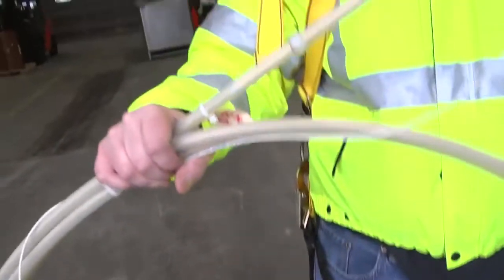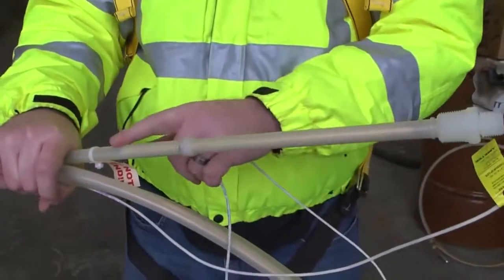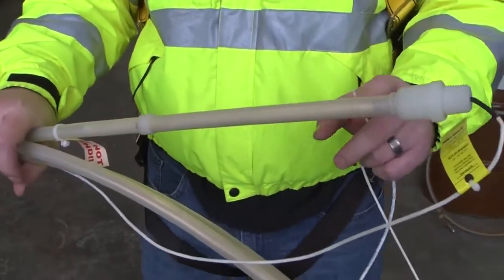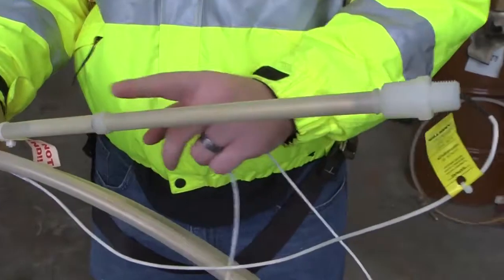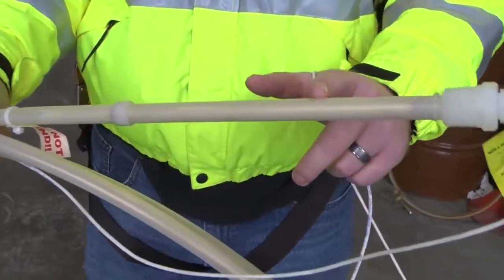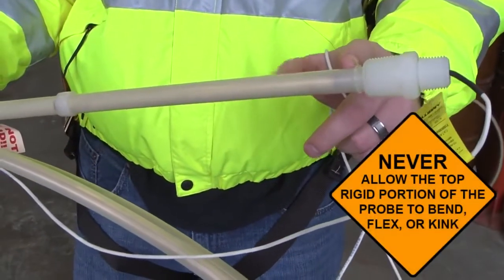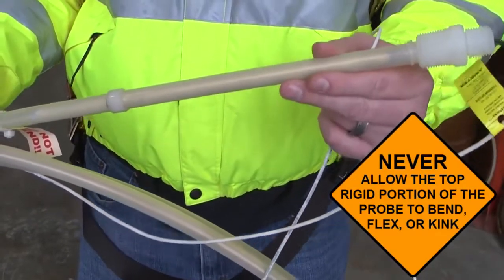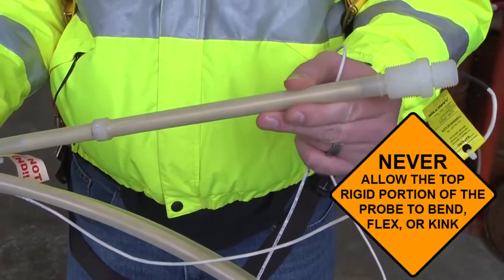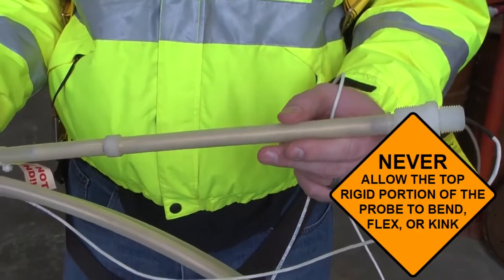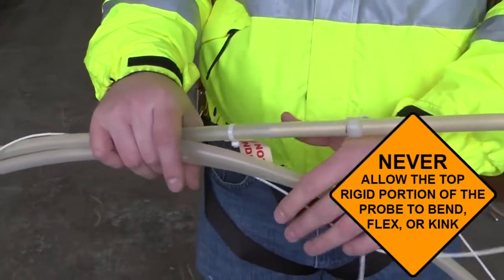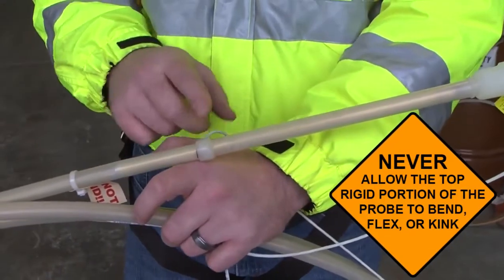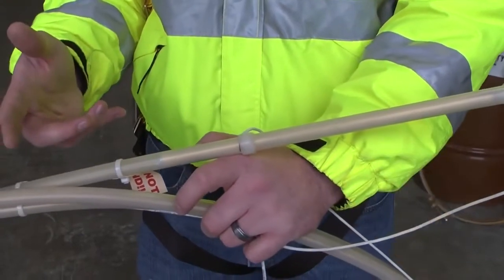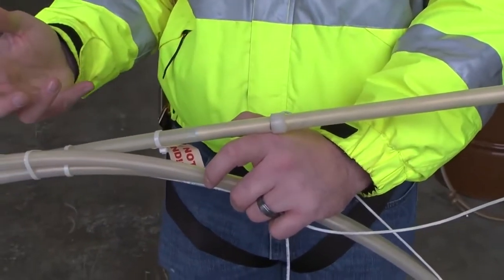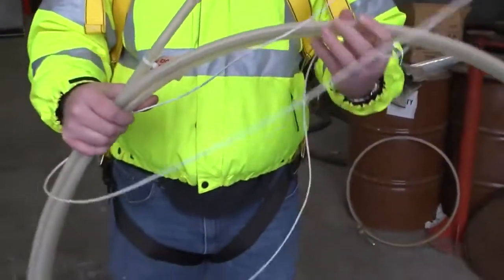If you see in this piece right here, this is a very rigid piece on the probe. This is very important. This is where the electronic head of the probe is. It reads the magnetic wire and does a communication back to the tank gauge. You must make sure that you never bend this piece. If you bend it, the probe itself may function, but you're only going to read a very short section of the probe. We'll say that the probe is maybe 2 or 3 inches long, or you'll get a really high invalid product height.